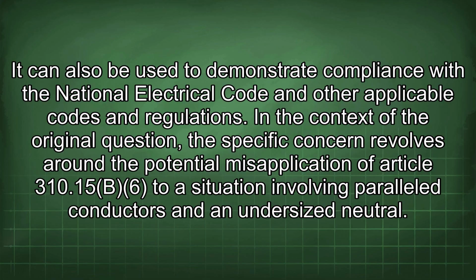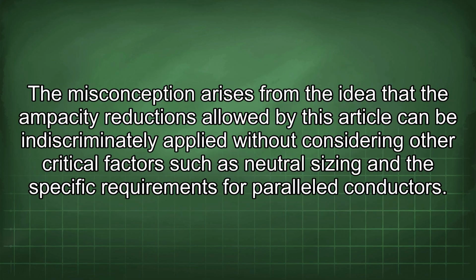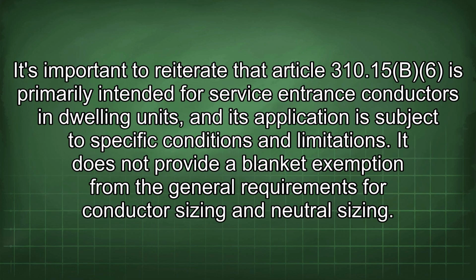In the context of the original question, the specific concern revolves around the potential misapplication of Article 310.15(B)(6) to a situation involving paralleled conductors and an undersized neutral. The misconception arises from the idea that the ampacity reductions allowed by this article can be indiscriminately applied without considering other critical factors such as neutral sizing and the specific requirements for paralleled conductors. It's important to reiterate that Article 310.15(B)(6) is primarily intended for service entrance conductors in dwelling units, and its application is subject to specific conditions and limitations. It does not provide a blanket exemption from the general requirements for conductor sizing and neutral sizing.